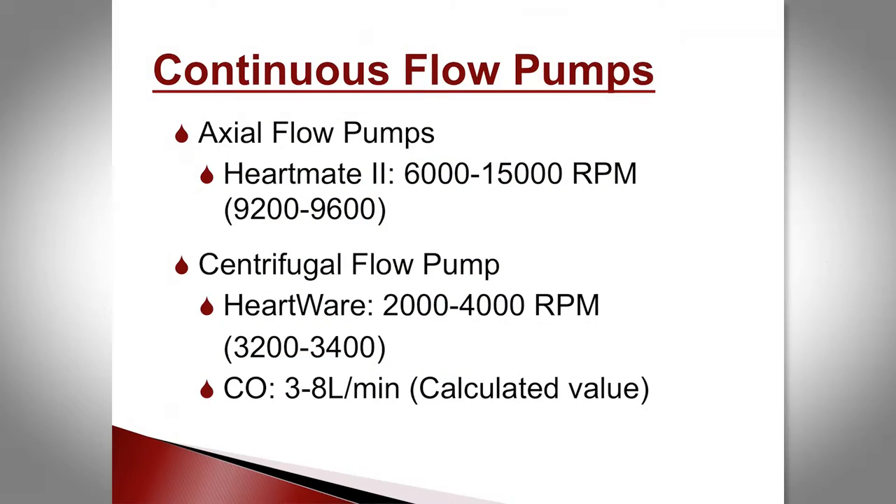For the HeartMate 2, we run it usually between 9,200 and 9,600 RPM. The HeartWare runs at 3,200 to 3,400 RPM, and flow ranges from 3 to 8 liters per minute. The flow is calculated — not truly measured — based on in vitro and in vivo studies correlating RPM and power to expected flow output.